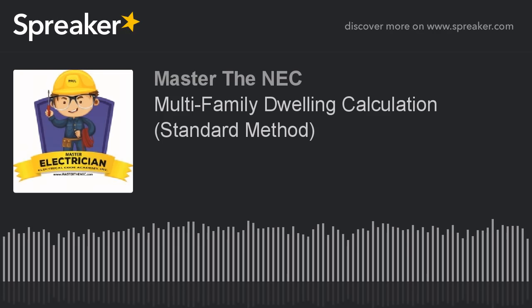Now, good news. When we're doing the dryer, we're also going to be able to apply a demand factor because we get to add the total, since we're doing a service calculation here. We're not doing the individual unit here. We're technically doing it for service for 18 units. So we're trying to do the service for this entire condominium. So we're going to take 5,000 times 18.